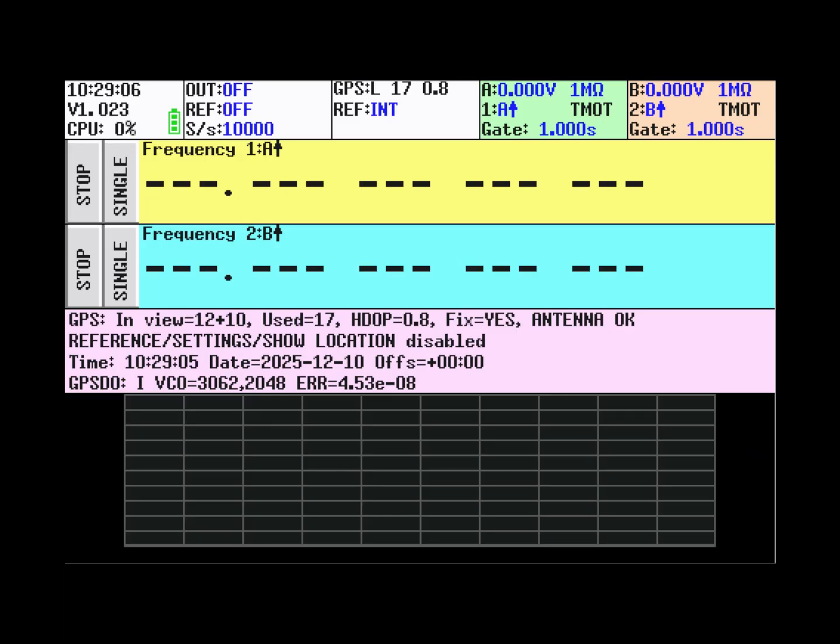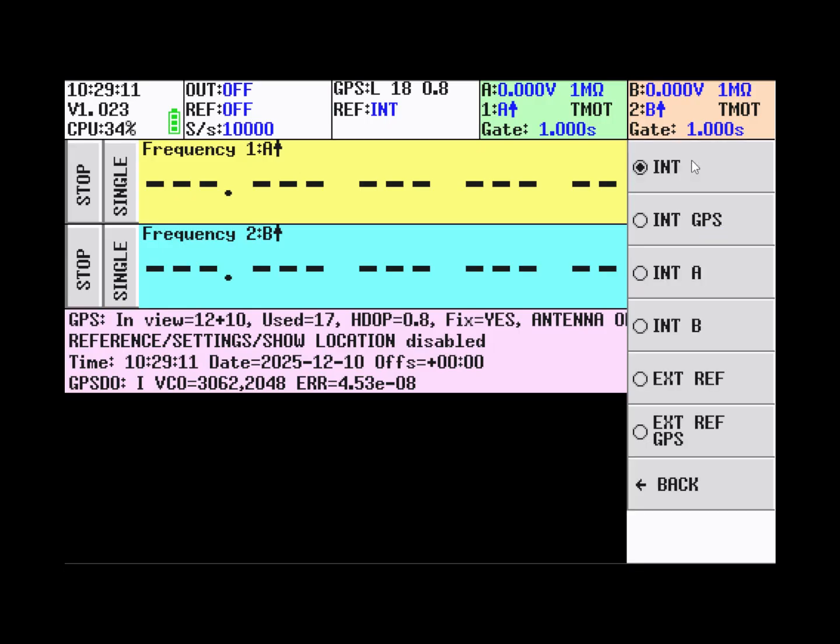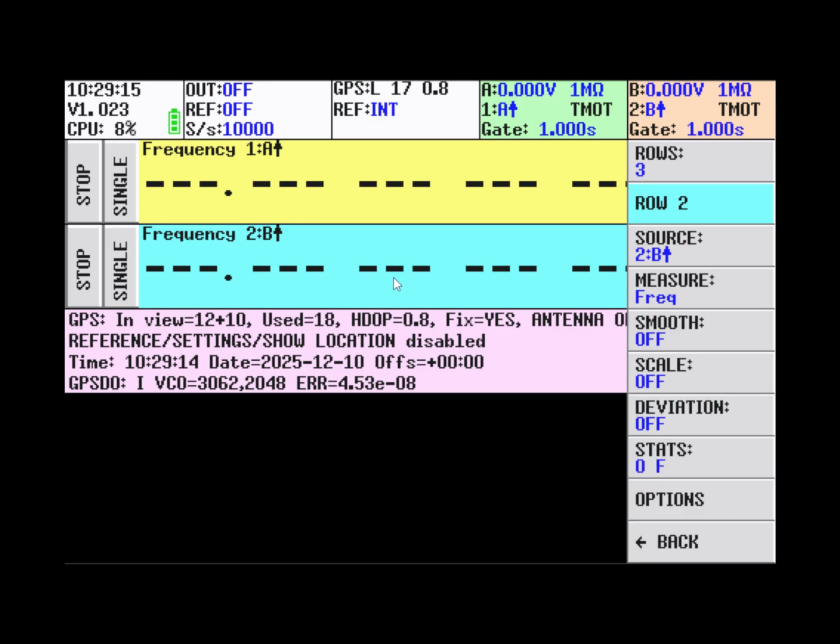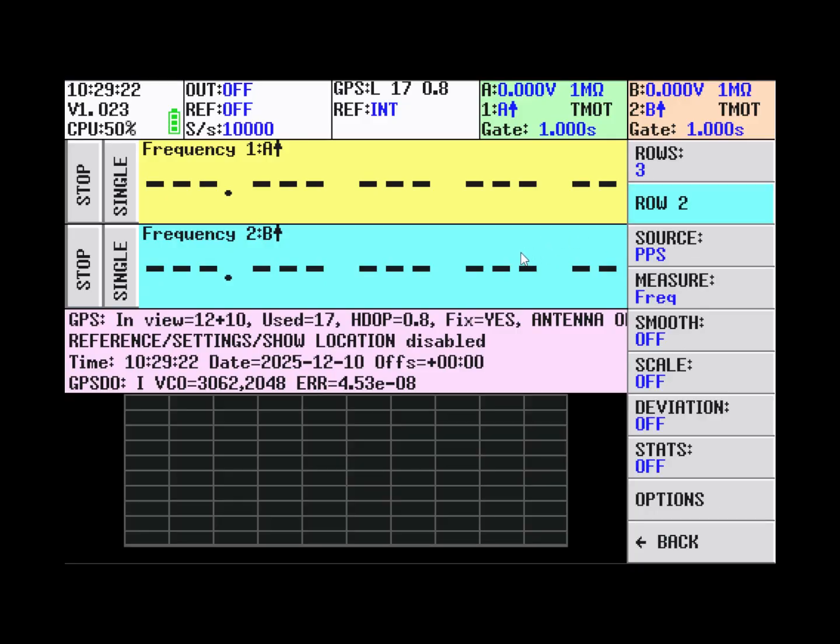Now we can switch the internal reference to become locked to the GPS. But before we do that, it's nice to show the process of locking by setting row 2 to measure the GPS PPS.